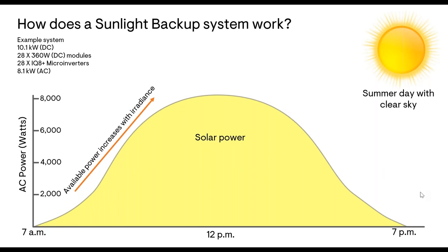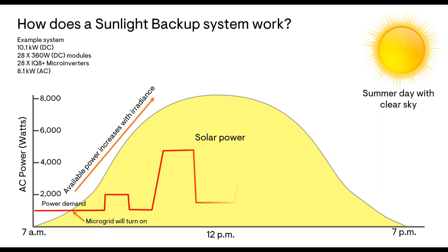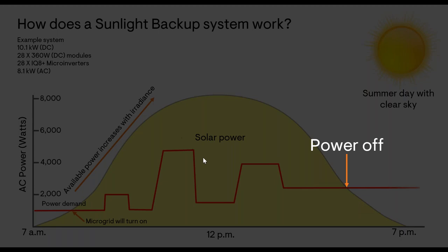It's a nice sunny day, and in the evening the sun sets and your power starts to go down as a result. That's pretty predictable if there's good sun. But how do people use energy in their house, and how do they use their loads? They're turning lights on and off. They might be running the coffee machine, running whatever, and the power demand just goes up and down as they use the loads in their house. But with sunlight backup, because there's no battery in this configuration, the second you need more power demand than what's available from PV, that system is going to shut down.